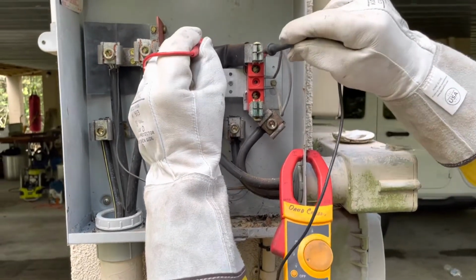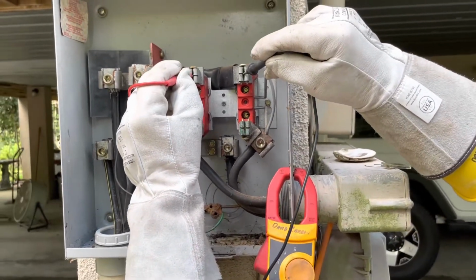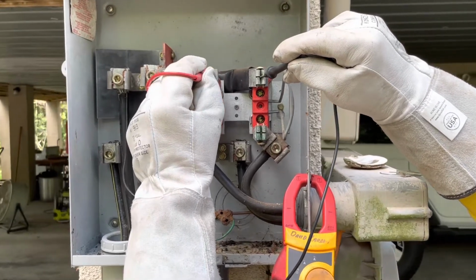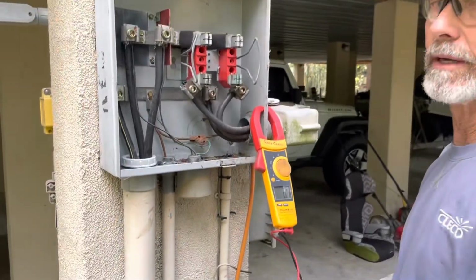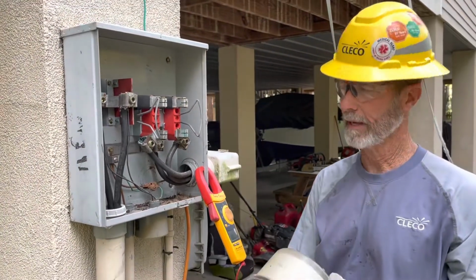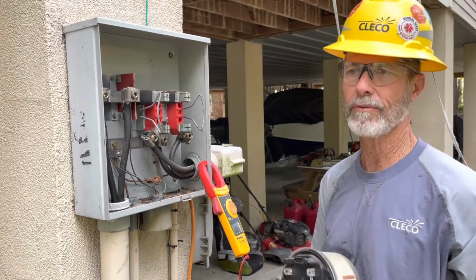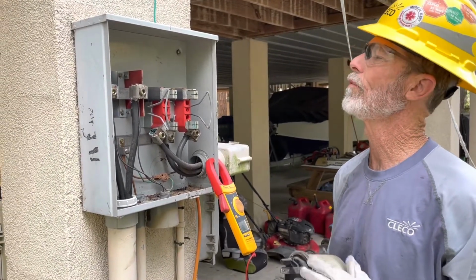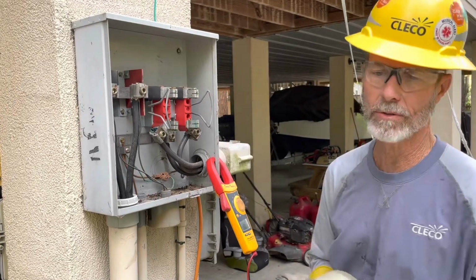I should have 240 volts. 246 volts. So this is to be metered by a Form 2S meter. It's a 120/240 volt service. Okay, we're gonna plug this meter back in. The voltage was good. We know it's a single phase 120/240 service because I had the correct voltages.